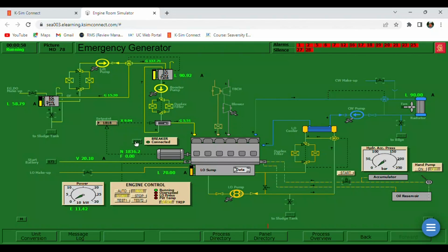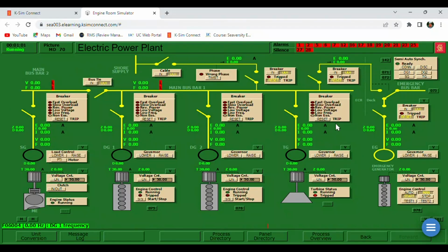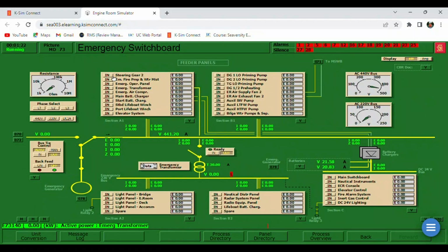So I'm going to go to the switchboard, put the voltage controller on, and put the controller in automatic. This should automatically connect to the emergency bus bar. Okay, now it's connected. So I'm going to put all the breakers in the emergency switchboard to in. Okay.